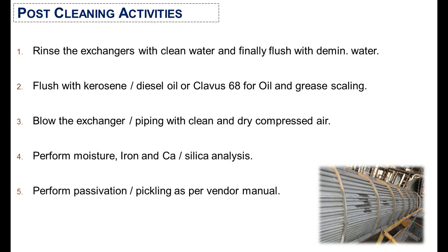For exchangers having depositions of oil or grease, after cleaning, flush with kerosene, diesel oil or Clavus 68. Then blow the exchangers or the piping with clean and dry compressed air, and also perform moisture, iron, calcium or silica analysis from the samples.